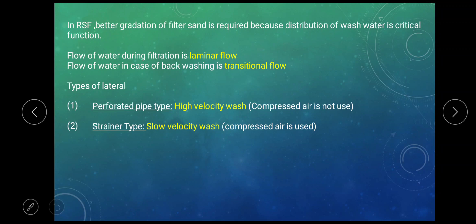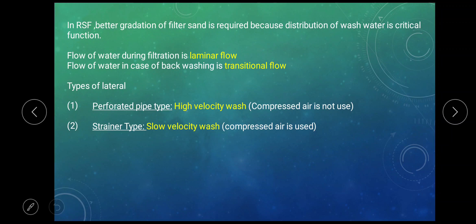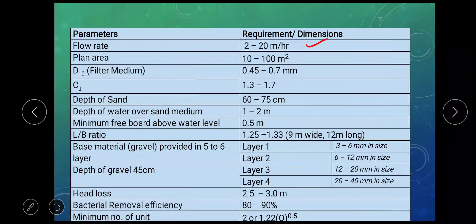In rapid sand filter, well-graded sand grains are used as distribution of wash water is one of the critical functions. Flow of water during filtration is in laminar flow; however, flow of water during back washing is in transitional flow. The type of laterals used in the rapid sand filter may be perforated pipe type or strainer type. Perforated pipe type may have high velocity wash; however, strainer type may have slow velocity wash. There are various parameters and recommended values. Flow rate, that is filtration rate, may vary from 2 to 20 meter per hour. Since the filtration rate is very high, a very small surface area of the filter is needed.